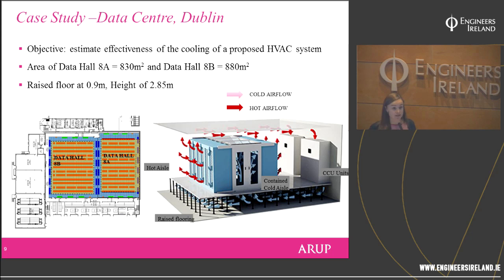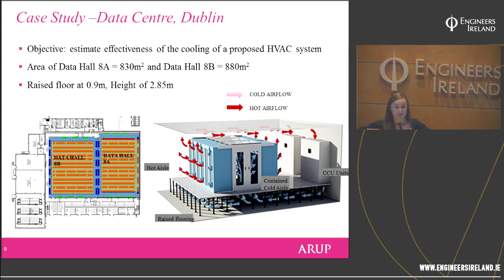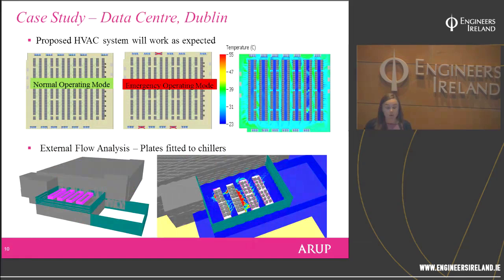A recent project was a data centre in Dublin with two data halls, A and B, of similar size. Typically in data centres there's a raised floor — cold air passes underneath and comes up to cool the computer units, then returns to the cooling unit to be recirculated. That's how data centres are typically cooled.